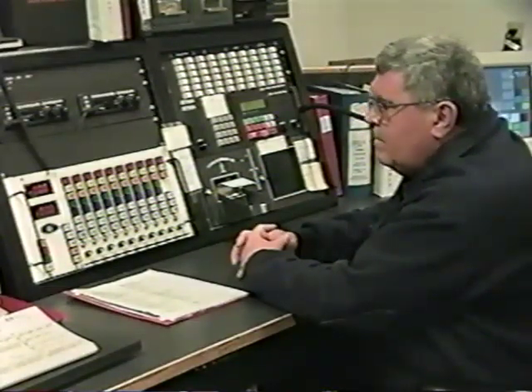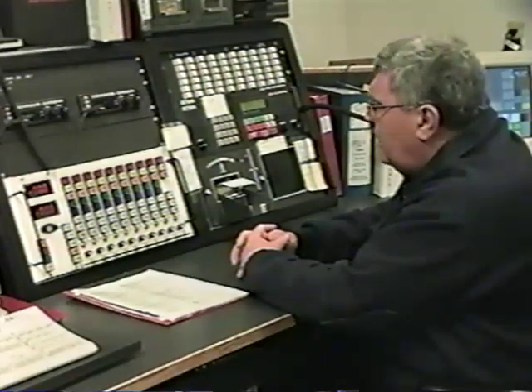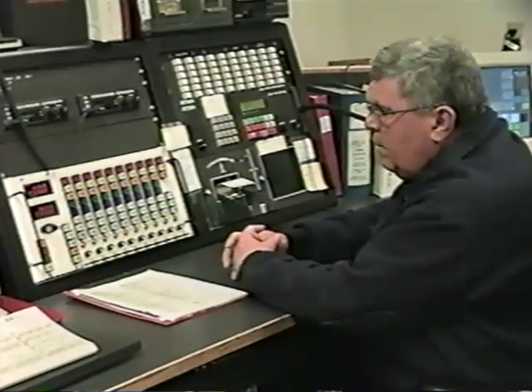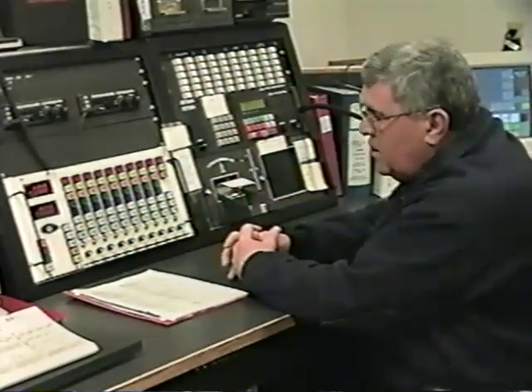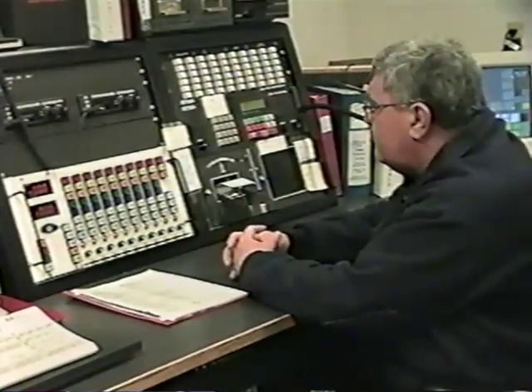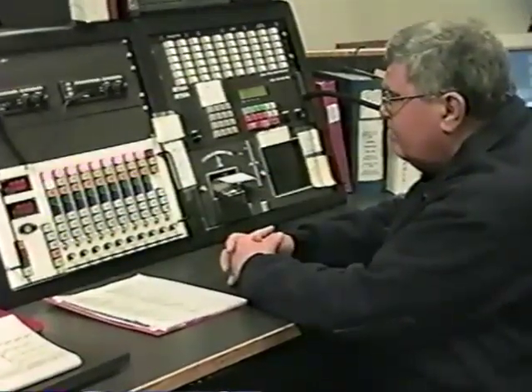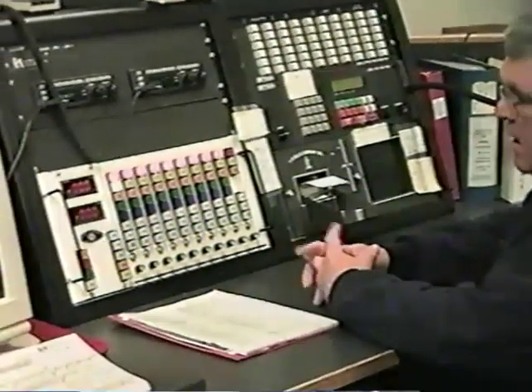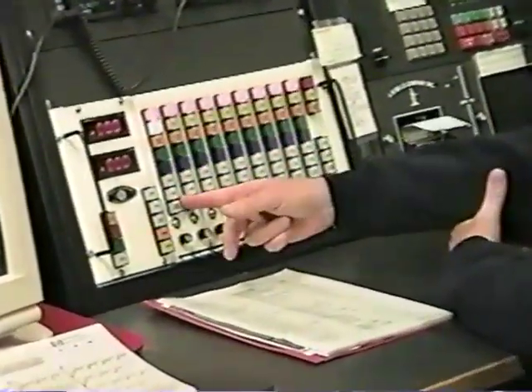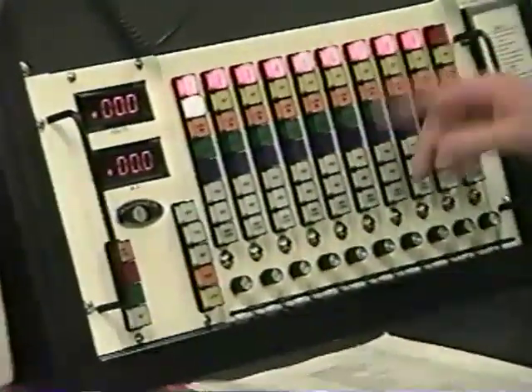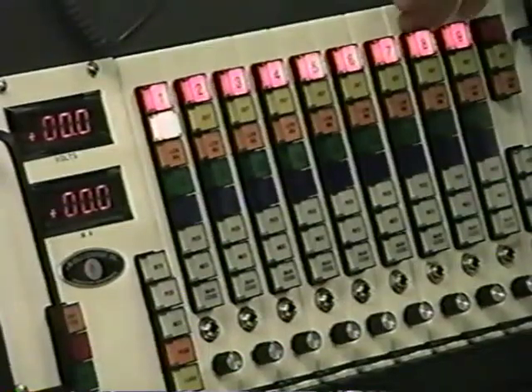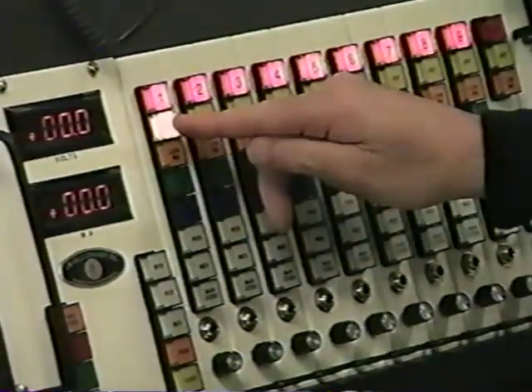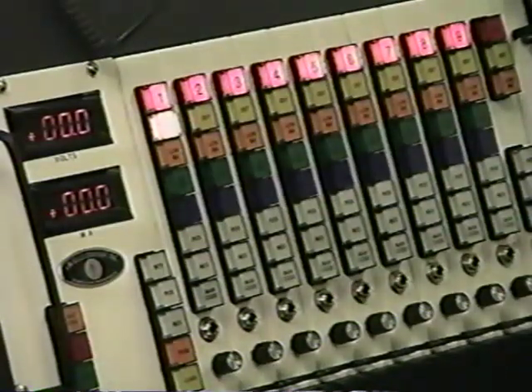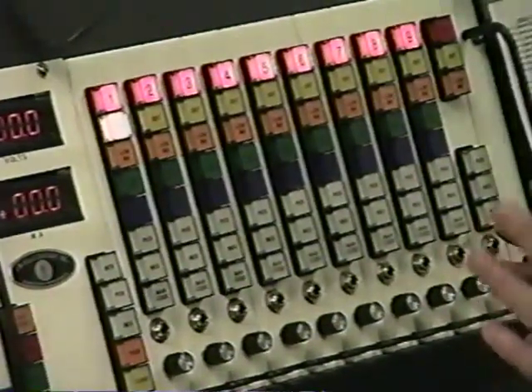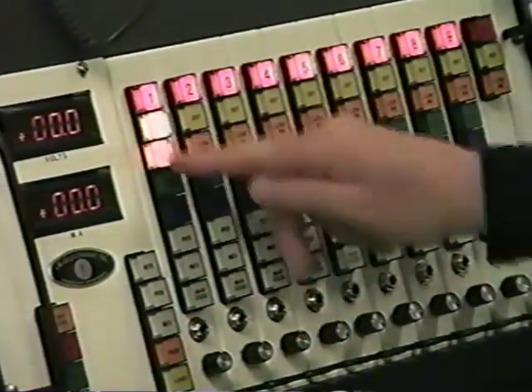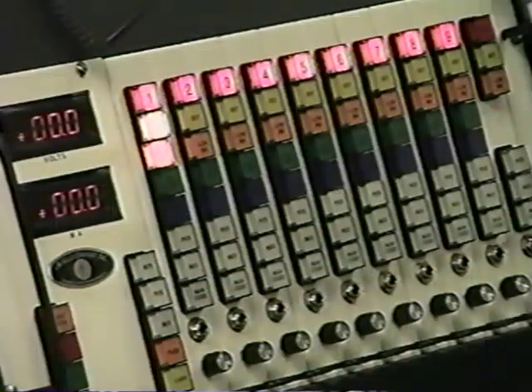What I'd like to do is simulate a problem that could arise with the system. You could be sitting here minding your own business, and all of a sudden something happens on the street and a wire breaks, and it's going to open a circuit. You can see here that circuit one opened up. The reason the other lights are lit is because it will repeat through all the circuits. But circuit one is open, we can tell by this light right here. That means that there's either something that has caused low voltage, and that's the low voltage light that's just come on, or that a wire has broken.